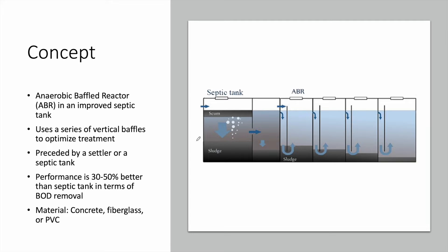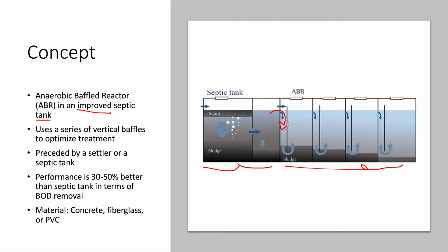The Anaerobic Baffled Reactor is considered an improved septic tank. It is a primary treatment system usually used for small to medium scale projects and is mainly considered a decentralized wastewater treatment system. It consists of a normal septic tank followed by many vertical compartments with a series of vertical baffles, ensuring better performance — about 30 to 50 percent more removal of BOD compared to a standard septic tank.